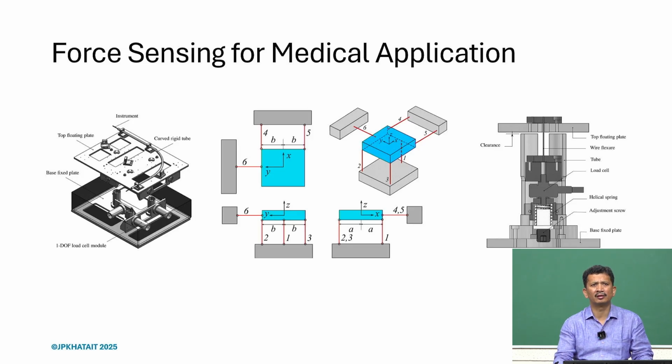What happens if a flexible instrument interacts, and what kind of forces does it exert? Suppose you want to characterize any kind of catheter or endoscope or flexible instrument, when we manipulate these instruments and they interact with the tissues, what kind of forces are there? For the characterization, if you want to measure these forces, it's very important that we are able to measure them precisely. Many times these forces are very small, so the setup has to be sensitive.